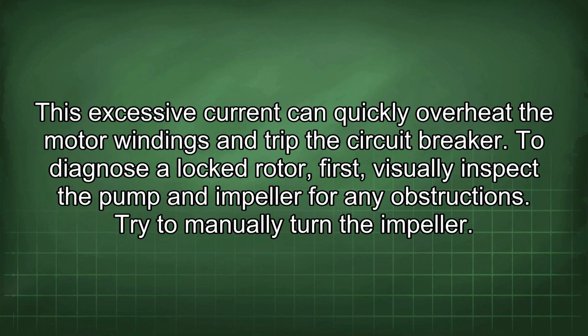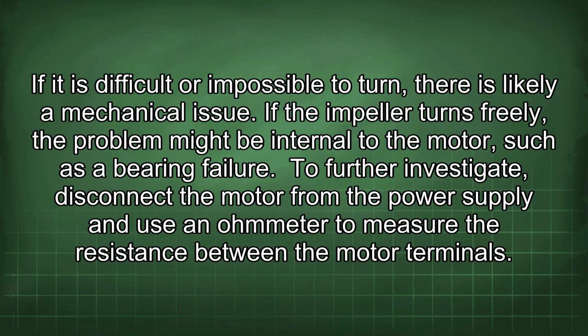To diagnose a locked rotor, first, visually inspect the pump and impeller for any obstructions. Try to manually turn the impeller. If it is difficult or impossible to turn, there is likely a mechanical issue. If the impeller turns freely, the problem might be internal to the motor, such as a bearing failure.